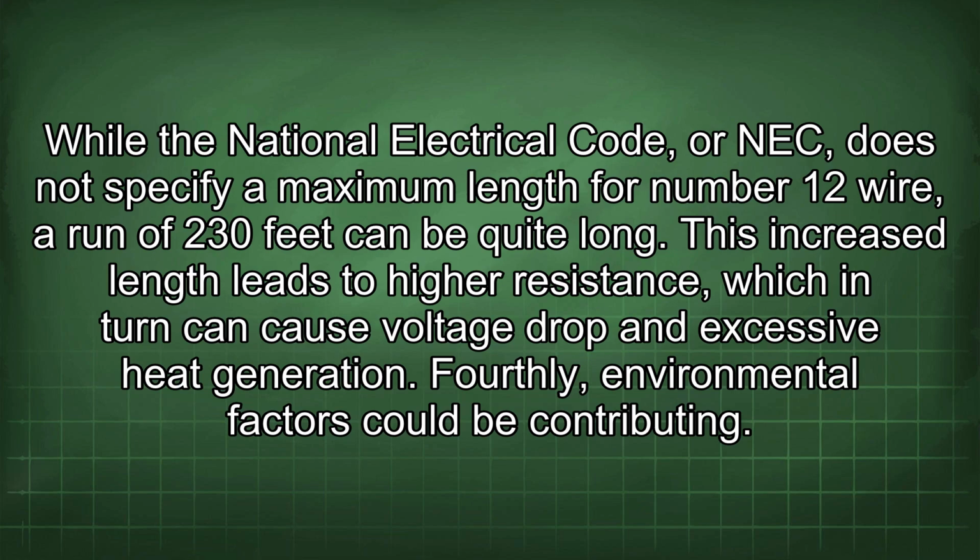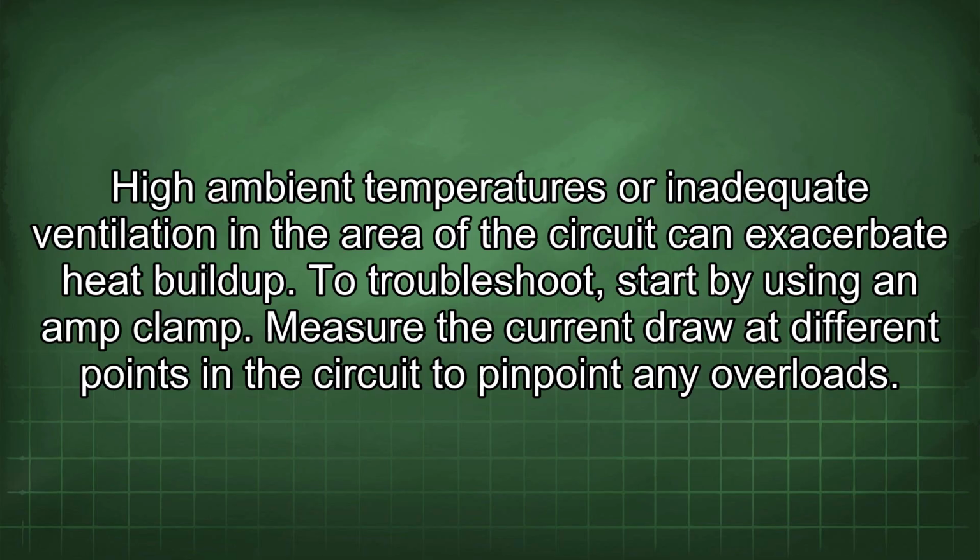Fourthly, environmental factors could be contributing. High ambient temperatures or inadequate ventilation in the area of the circuit can exacerbate heat buildup. To troubleshoot, start by using an amp clamp. Measure the current draw at different points in the circuit to pinpoint any overloads.